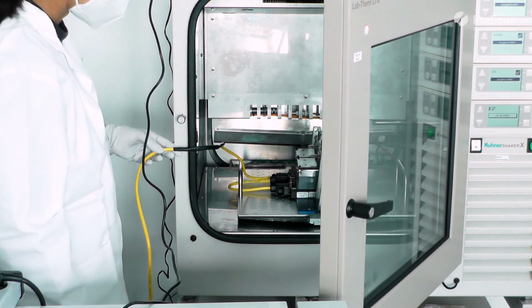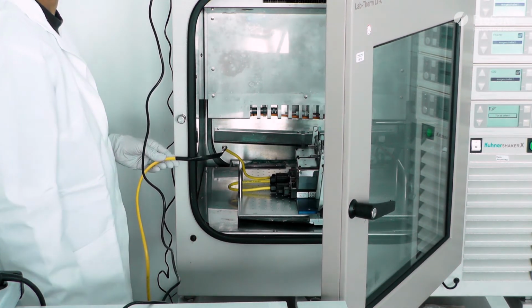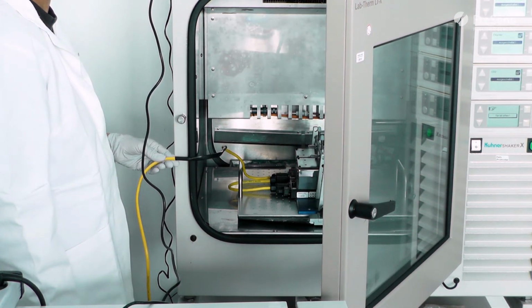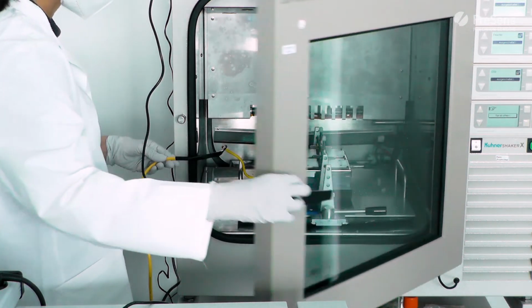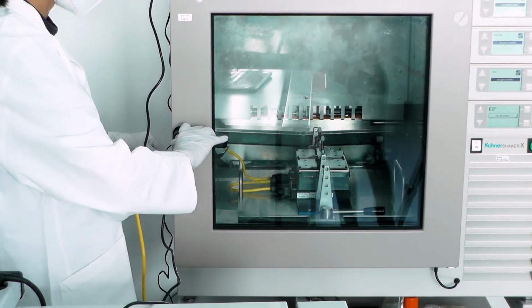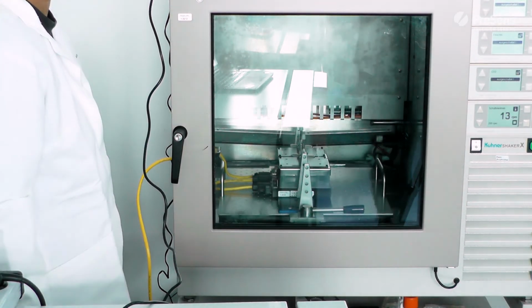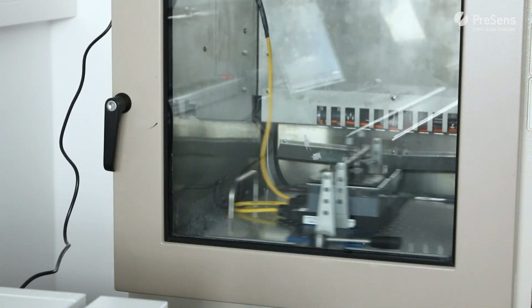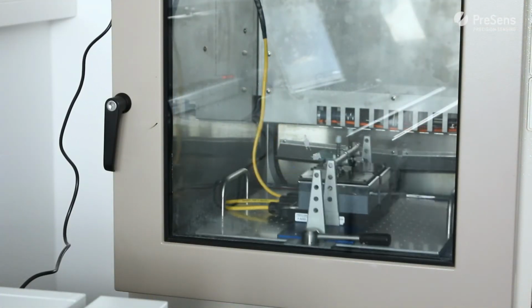If there is no access port in your shaker, the cable to the splitter can be led through the incubator door. The black flat part of the cable must be located at the door's ceiling, like shown here, to ensure the door closes properly. Take care that the cable is not bent unnecessarily and that it does not hit the incubator wall while shaking.